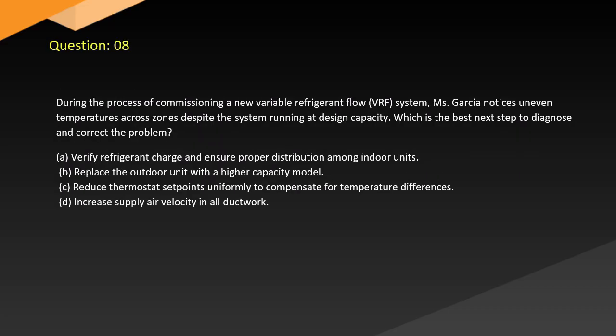Question 8. During the process of commissioning a new variable refrigerant flow, VRF, system, Garcia notices uneven temperatures across zones despite the system running at design capacity. Which is the best next step to diagnose and correct the problem? A. Verify refrigerant charge and ensure proper distribution among indoor units. B. Replace the outdoor unit with a higher capacity model. C. Reduce thermostat set points uniformly to compensate for temperature differences. D. Increase supply air velocity in all ductwork.